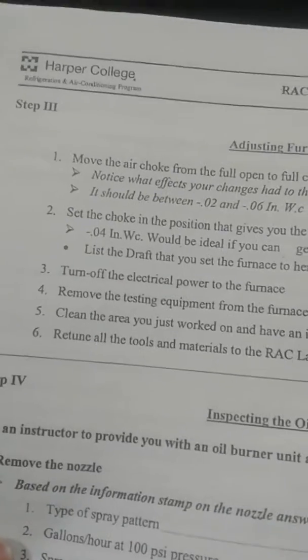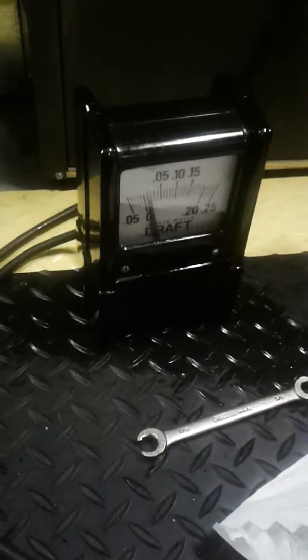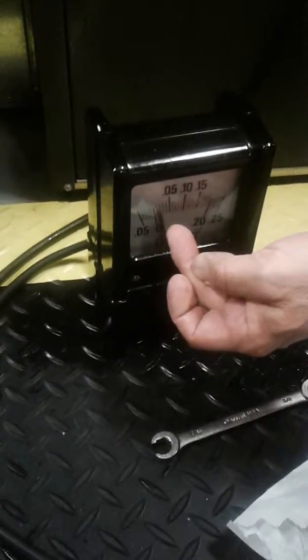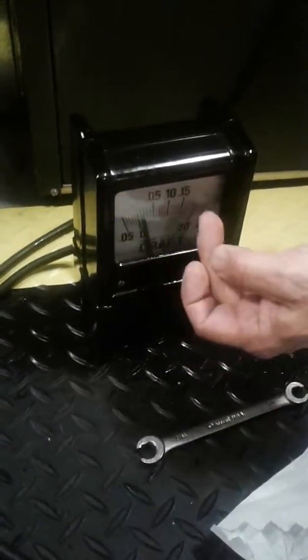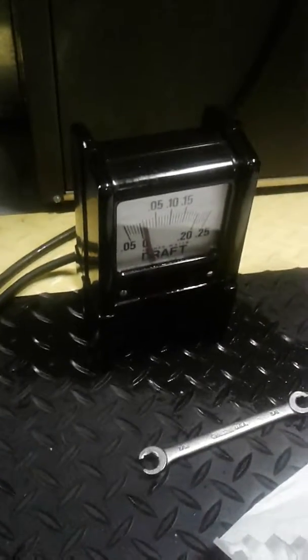It says here, set the choke position to give you the best draft. It should be between about negative 0.02 and negative 0.06, so we're trying to achieve around negative 0.04. So what I want you to do, guys, is adjust the choke and watch your draft gauge. It's actually went up, it's about 0.02. Anything below the line, the 0 is negative, anything above the line is positive. So it actually went up, so we should really open the choke a little bit more.